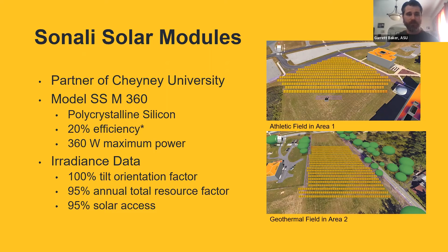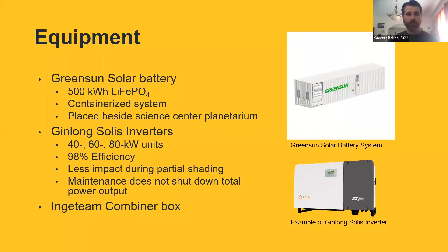A 500 kilowatt hour containerized battery system by Greensun Solar has been selected. The lithium iron phosphate chemistry will provide a longer battery life and depth of discharge of 80%. Ginlong Solis inverters are used with sizes of 40, 60, and 80 kilowatts. Ingeteam combiner boxes are used. Opting to use several inverters rather than one allows the system to operate continuously throughout maintenance, as well as better power output during partial shading.